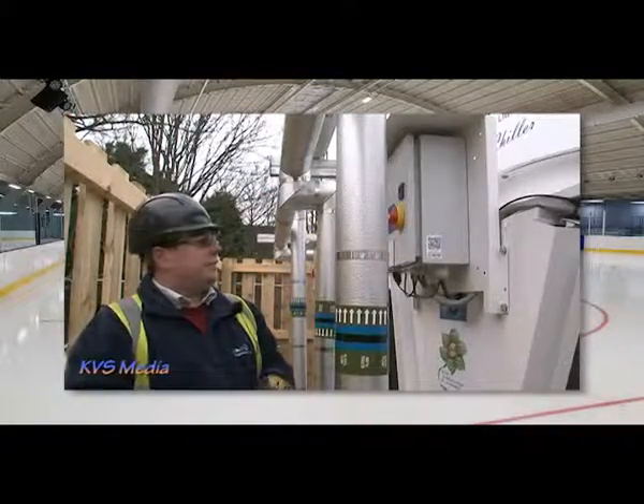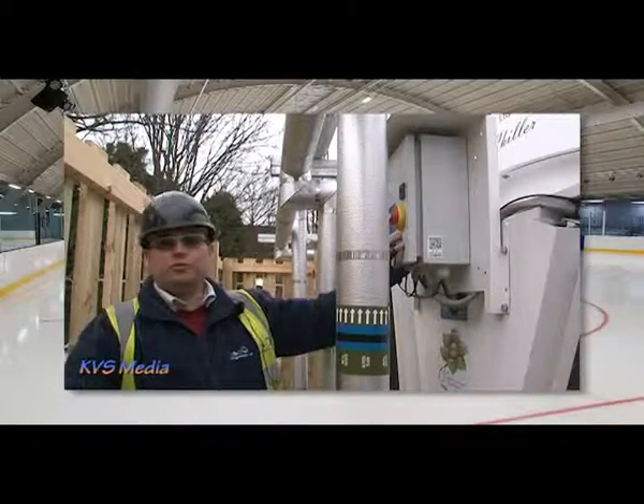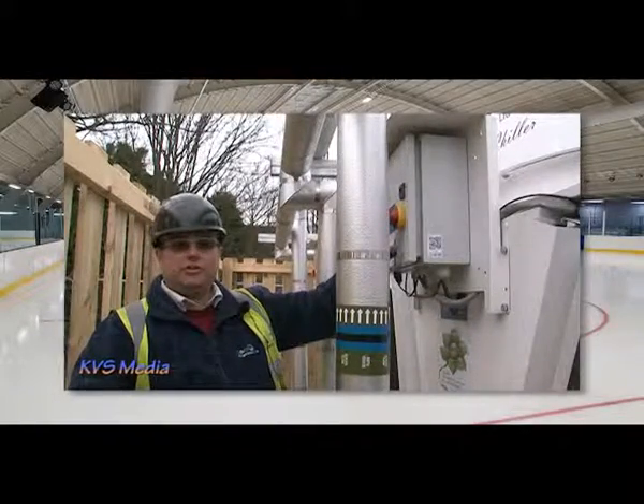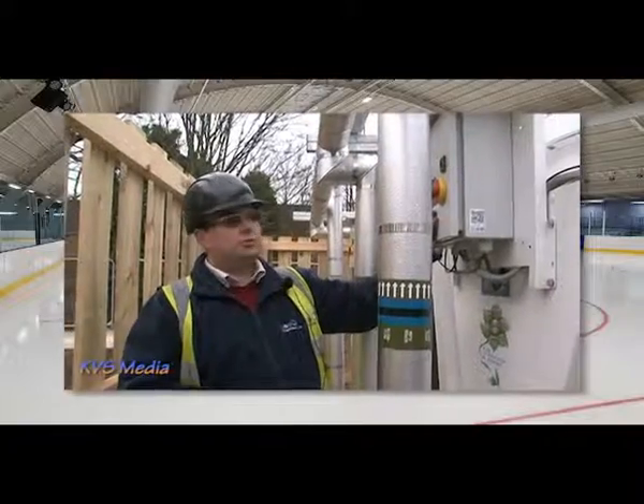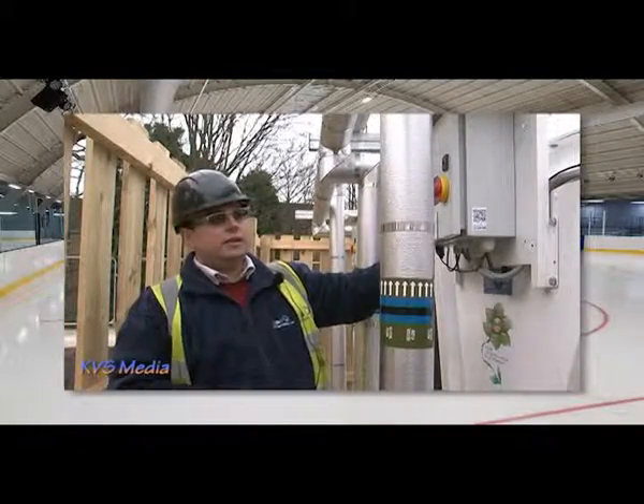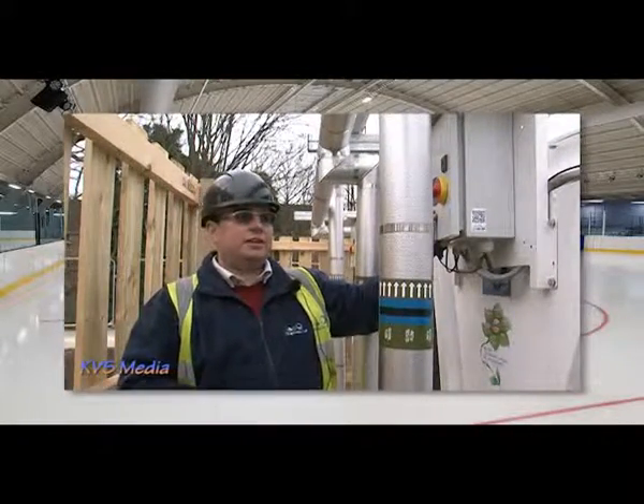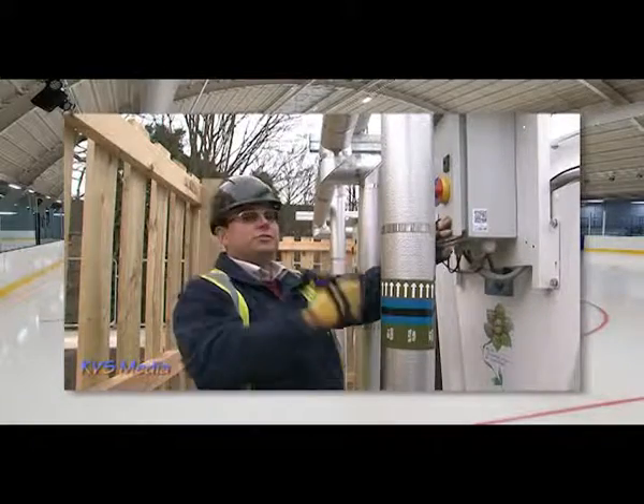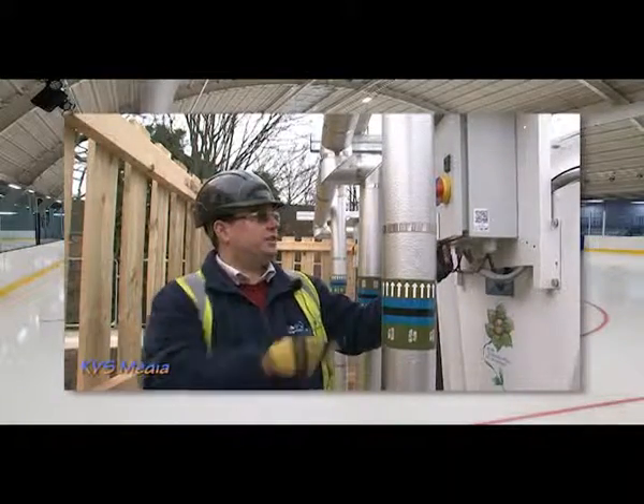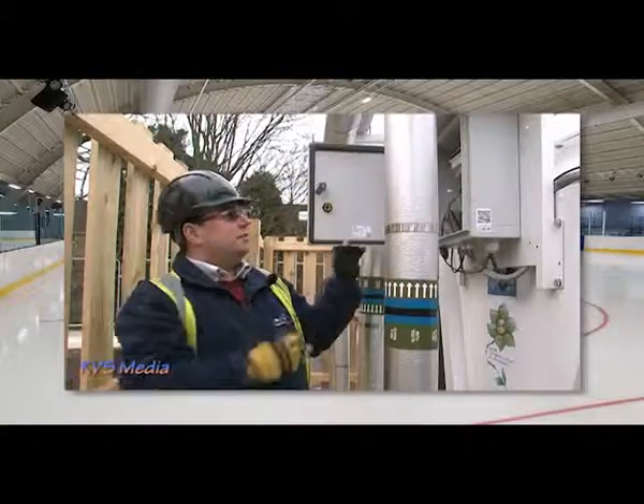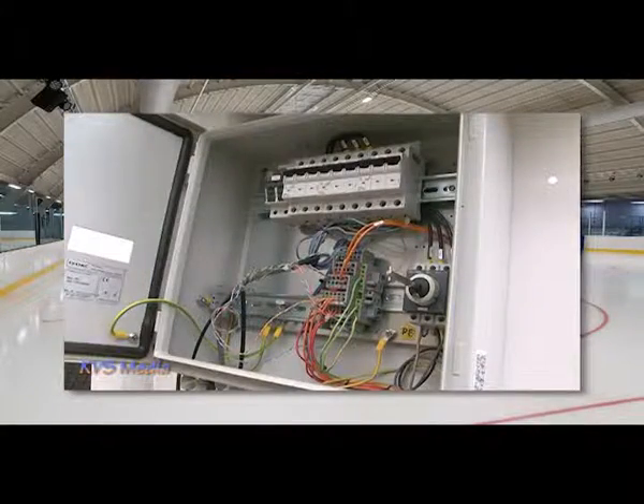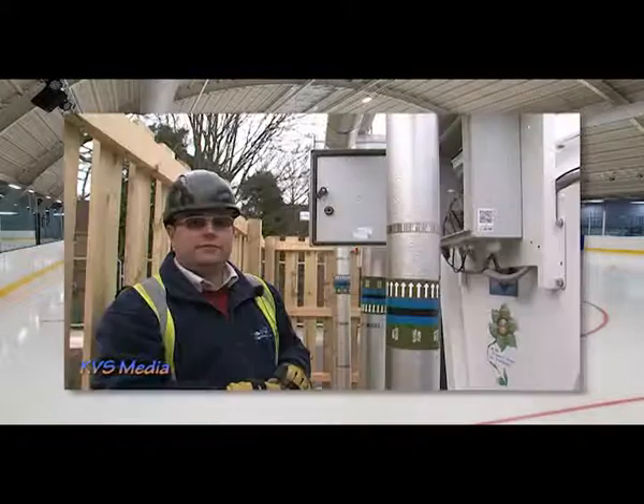At the end of the condensers here we have a small control panel which just has a local isolator on, which allows you to isolate the whole of the condensers. Each one of the fans has its own isolator. Within this control panel, which can be opened with a standard utility key, there is MCBs for each one of the fans, which can be manually reset if needed.